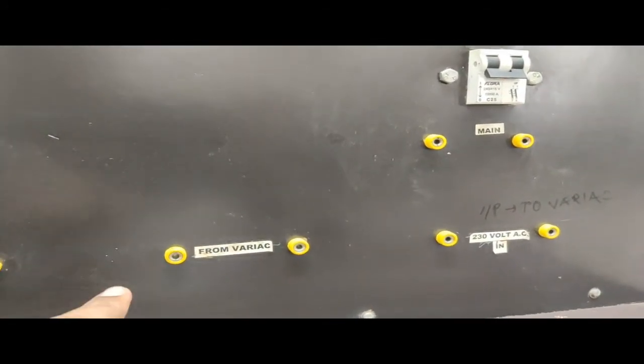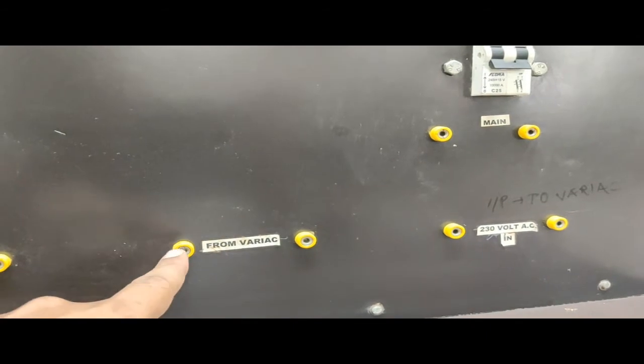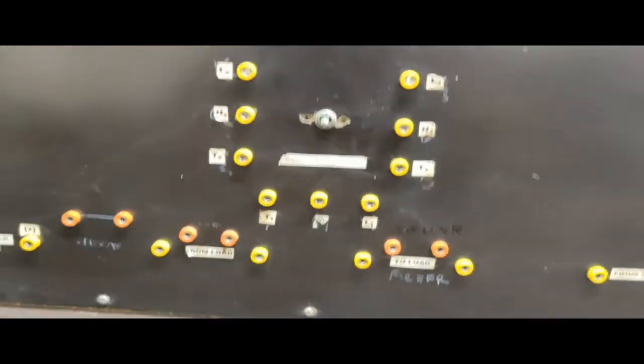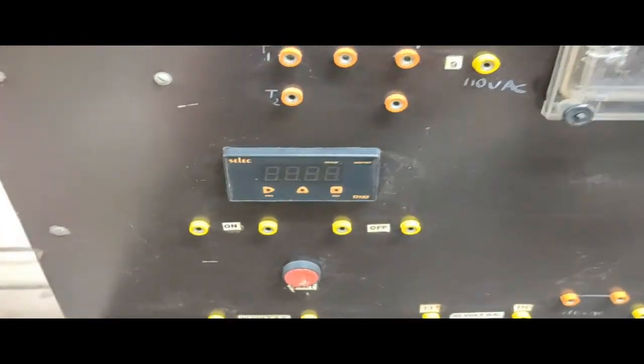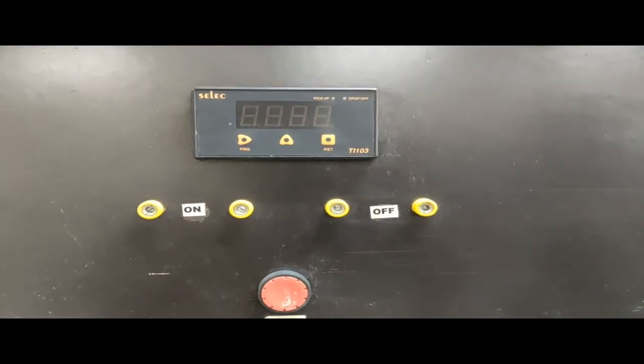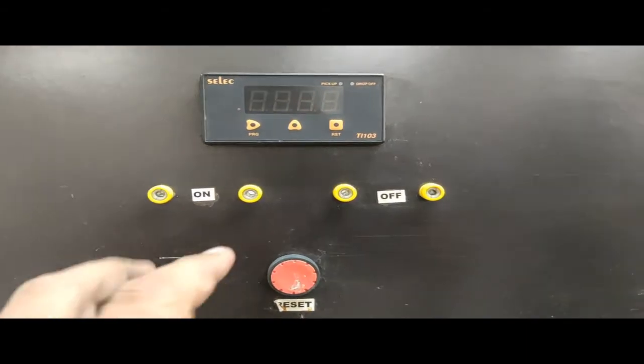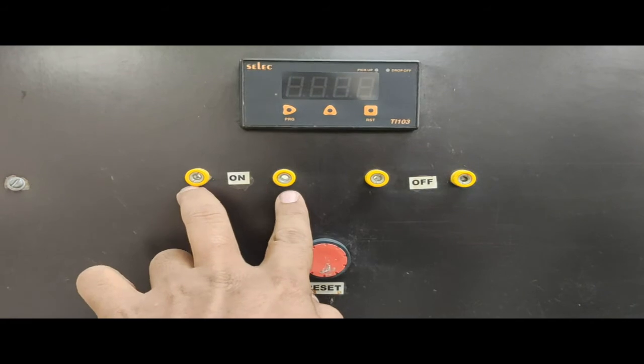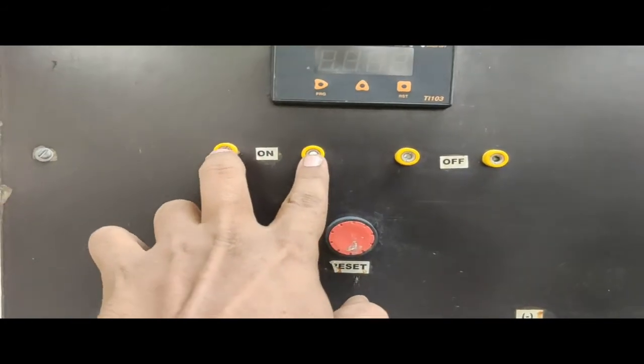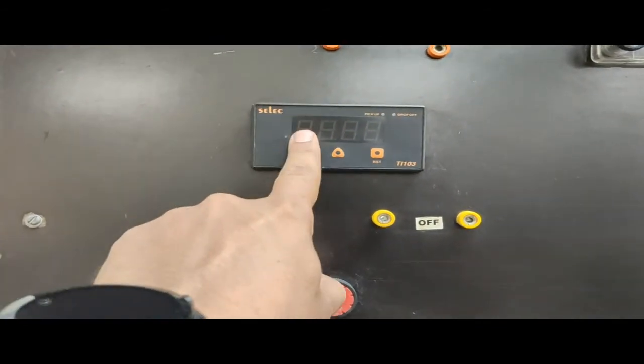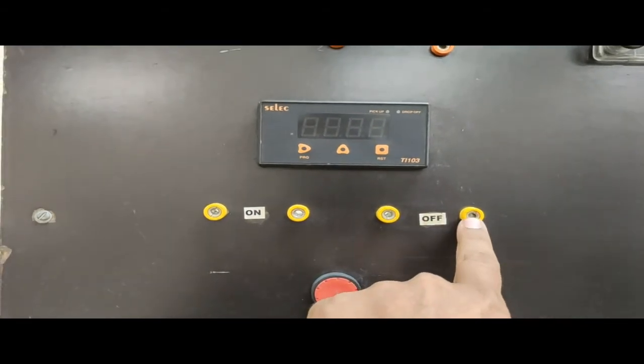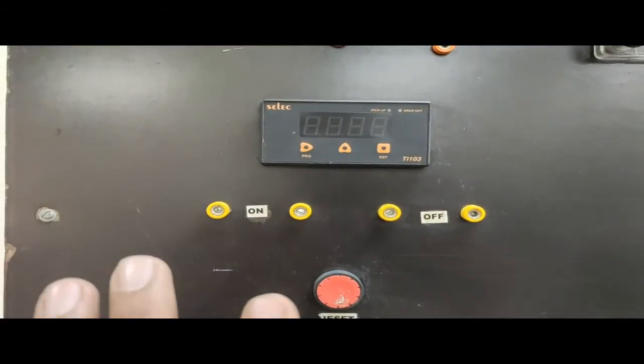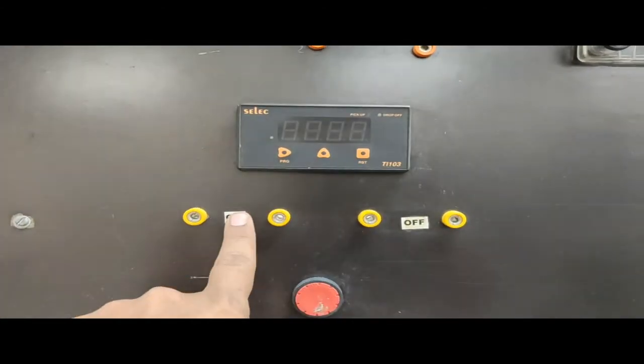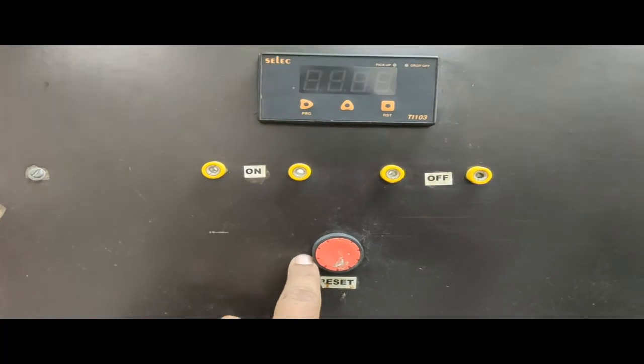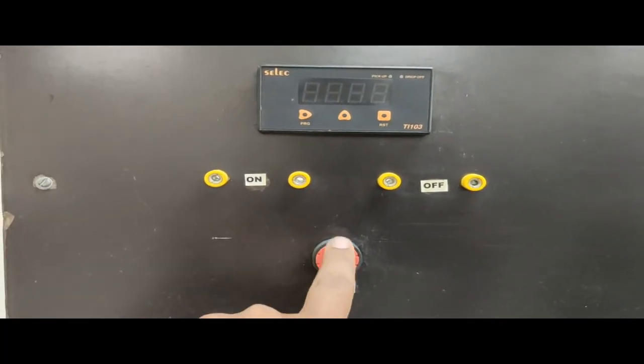Now here the variac is there, which means if I move the variac, different voltages will be applied here. Another thing here is the digital timer. To measure the operating time of the relay, this timer is required. Here you see this is a digital timer and 4 terminals are there, 2 for the on and 2 for the off. If I give a short circuit pulse to the on terminals, the timer will start, and when another short circuit pulse is applied to the off terminals, it will stop. This will be controlled by the relay and that by the switch, and this one is for resetting the timer. After every operation we need to reset the timer, so for that this switch is there.